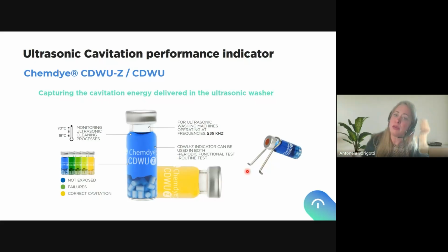If we are making a periodical test, this will use more indicators, but will be less frequent. If we use it for routine, every time we change the solution, we have a new situation, new water, new temperature, new detergent. So we should test it again with fewer indicators because, of course, it's just a routine. Just to make sure that in different locations, the cavitation energy is right.